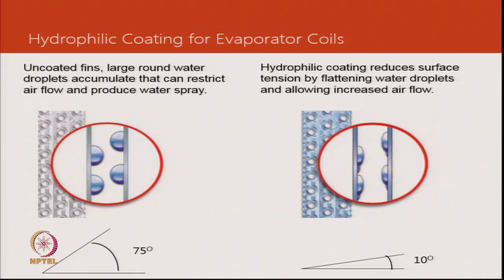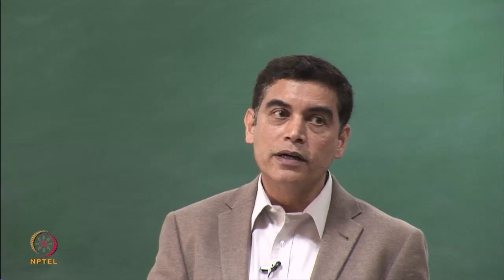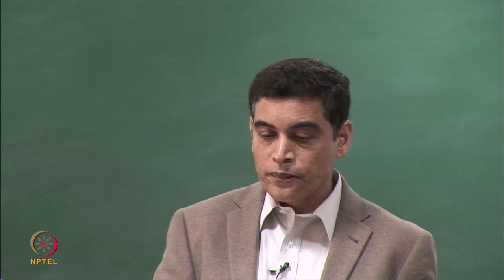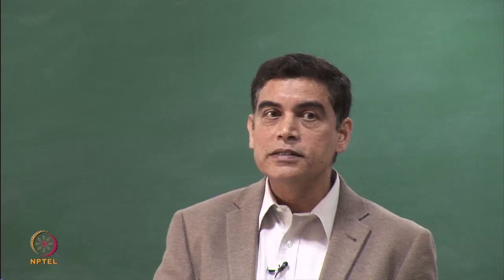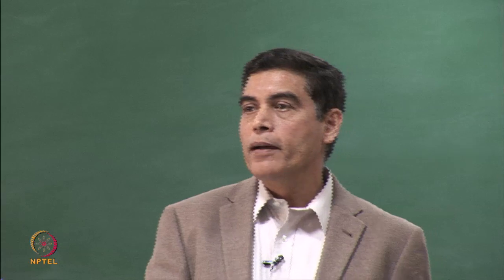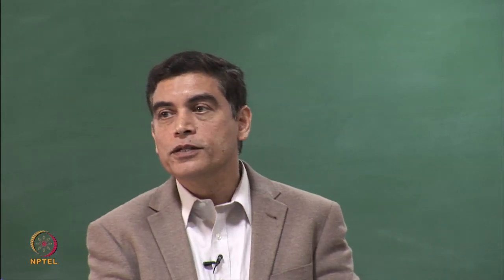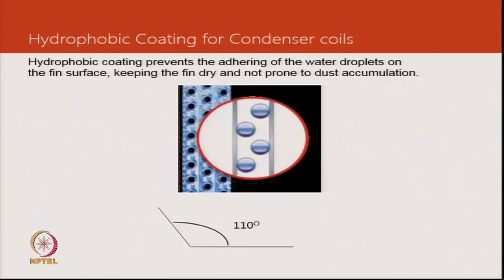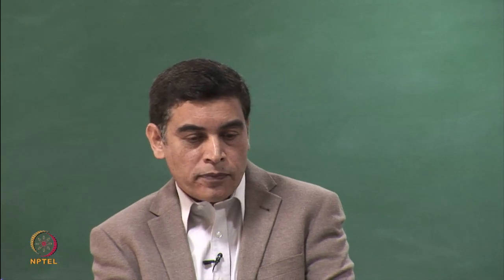The droplets being thrown in a tangential blower because of the velocity being high in certain part of the coil, it addresses very well. So, split systems you will normally see split systems have a blue coil, and that is an indication that a hydrophilic coil has been used there. And a split system has a tangential blower, so it would have a tendency to pick up droplets more than a window air conditioner or a ducted air conditioner chiller.